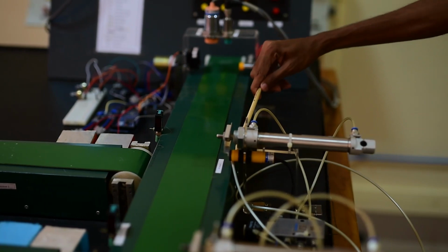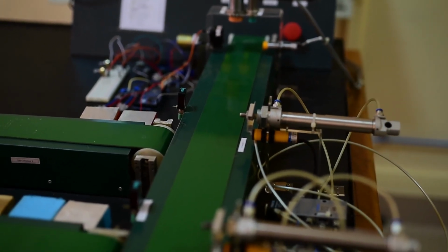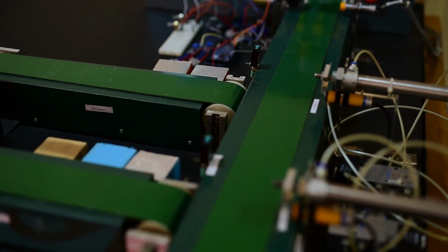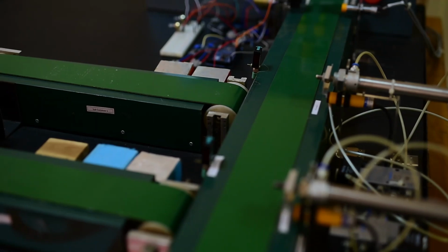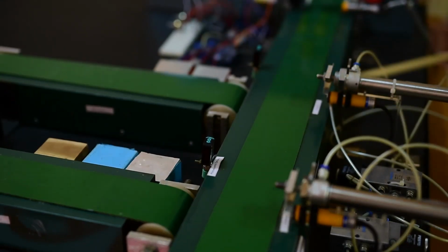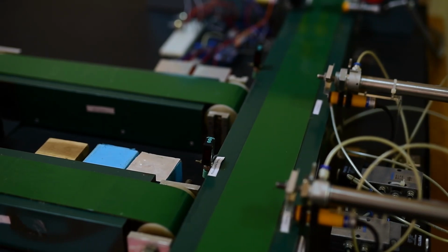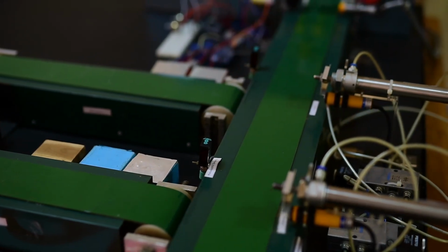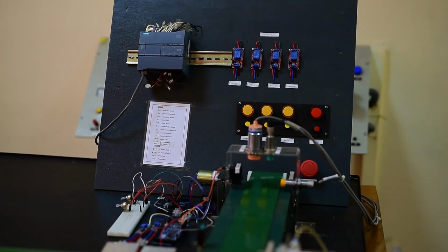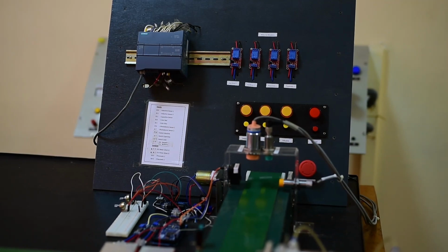A little away from the sensor arrangement, you can see 2 IR sensors which are placed right below the pneumatic actuators to detect objects that have arrived in front. Similarly, photoelectric sensors produce a signal when an object arrives at the initial point of the sub-conveyors. All the above sensors, except for the color sensor, have signals directly interfaced with the controller, which operates at 24 VDC.